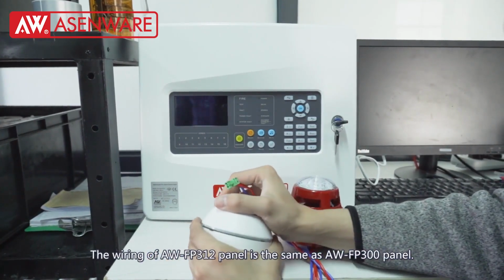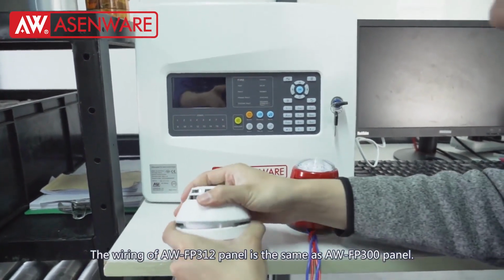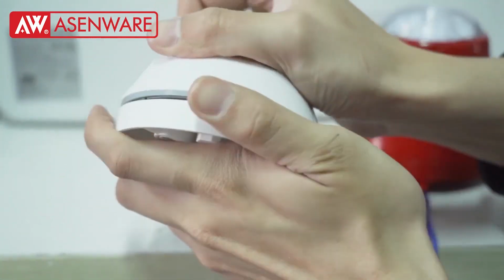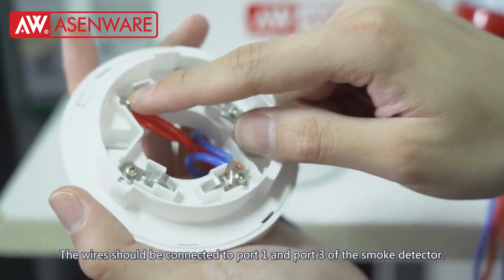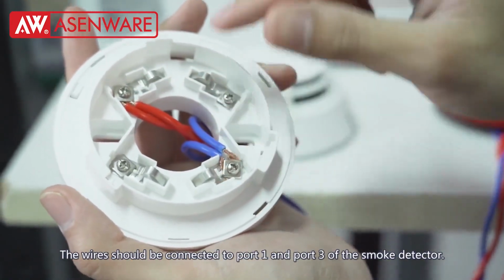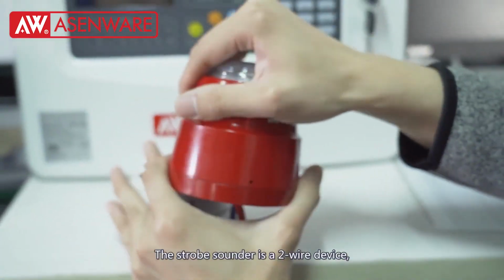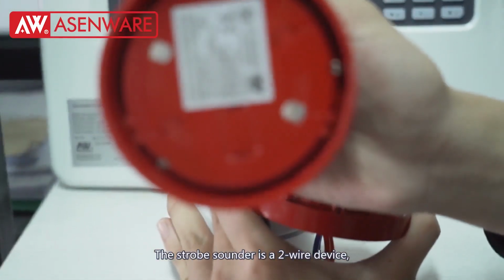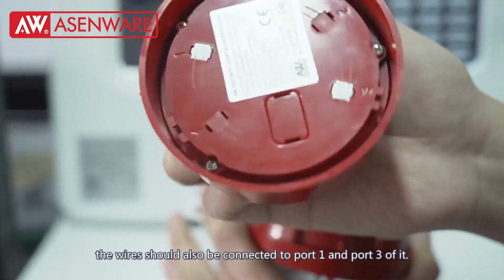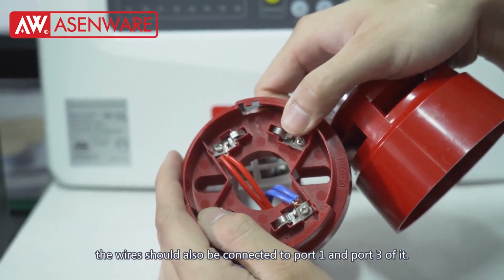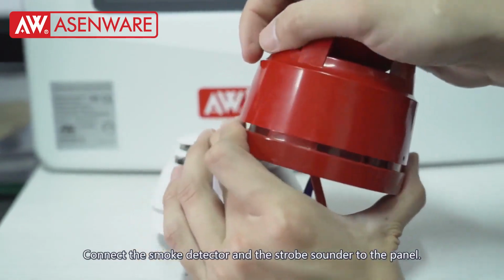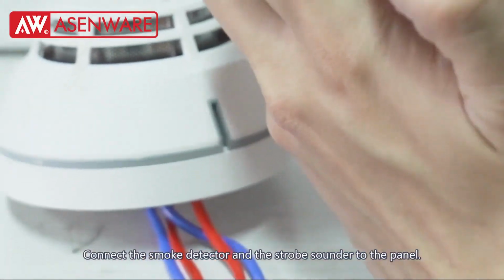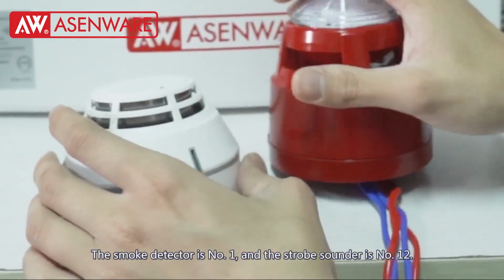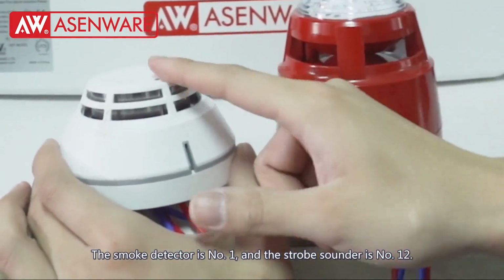The wiring of AWFP312 panel is the same as AWFP300 panel. The wire should be connected to port 1 and port 3 of the smoke detector. The strobe sounder is a 2-wire device. The wire should be connected to port 1 and port 3 of it. Connect the smoke detector and the strobe sounder to the panel. The smoke detector is number 1, and the strobe sounder is number 12.